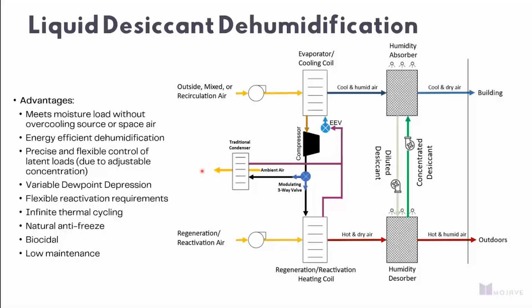So a couple other things here. Liquid desiccant, unlike solid desiccants, for anyone who is familiar with solid desiccants, will thermally cycle infinitely. The reason for that is just a crystalline salt structure. Again, it's a biocidal and natural antifreeze as well. From a maintenance perspective, liquid desiccant being a situation where it'll thermally cycle infinitely, never needs to be replaced. And through elegant engineering, which I'll talk about in a second here, it never needs to be topped off or what have you either.